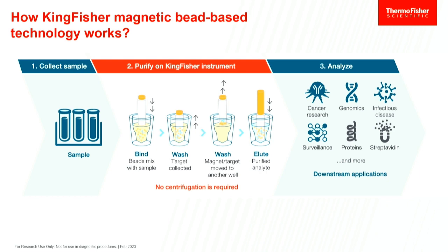The best method for working with magnetic beads is a bead movement process, and that's what the Kingfishers do. We bind our target with the beads, and instead of pulling those beads down with a magnet statically, we have a magnet on the instrument that collects the beads and moves them from step to step. A plastic tip comb protects the magnet and sample, and can also be used as a plunger to thoroughly mix samples. Keeping this process simple — let go, mix, and collect your beads — gives good purification and yield. When you automate this way, everything is done on a specific script, so your reproducibility and consistency is maintained.